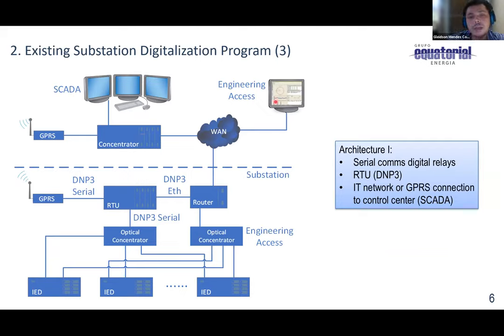At the same link, the IT link, is used by the engineering access that can collect logs and make configurations. It can access the same relay by a different port. So port A is used for monitoring the relay, the equipment, and port B of each relay is used for engineering access. So if you wanted to access the relay, it should be in a different port. So here we don't have a redundancy. If I lose this optical concentrator, I only have engineering access through port B. If I lose the engineering access, I only have the monitoring, but I don't have the remote access from outside the substation.